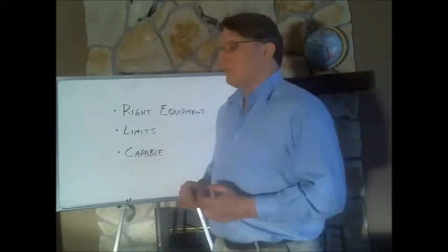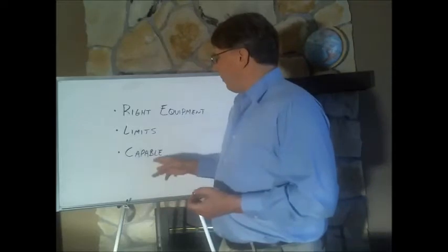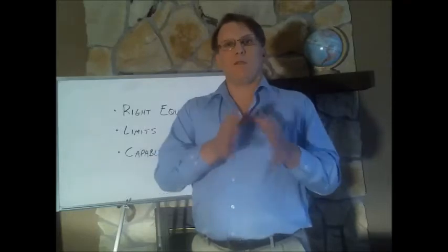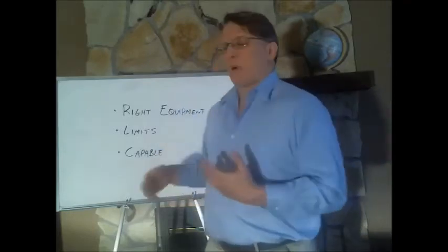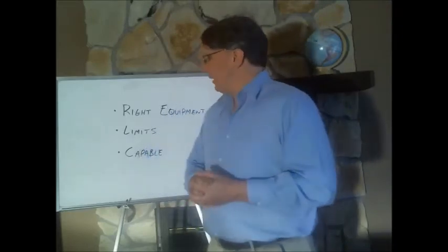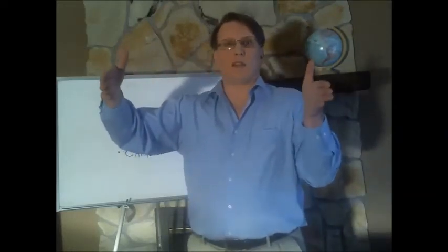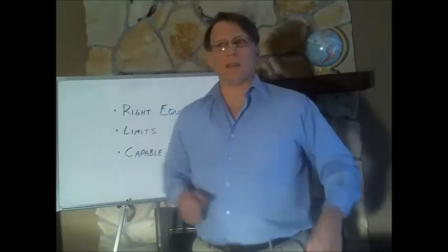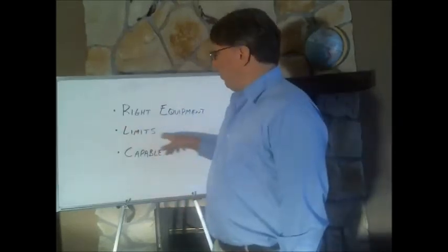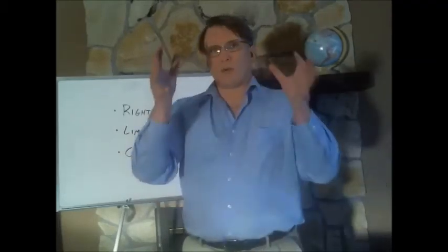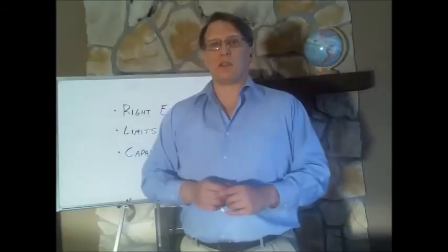The last thing: PQ, performance qualification, is basically about the capability of that particular process for a particular design. You start talking about process capability and understanding what it really does within the window of intended operation. You need to explore the limits here, because if you go just outside of those specs, the FDA or any customer is going to be concerned — do you fall off a cliff, or is it a gradual decay in performance? Why did you pick that limit? So we've explored what happens past the spec limits in the OQ, and now within the window, what happens?